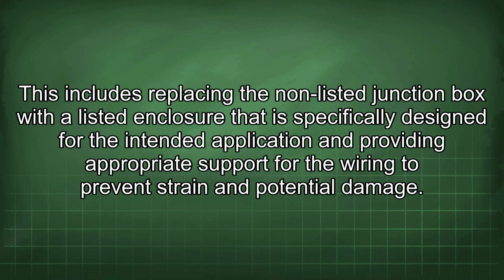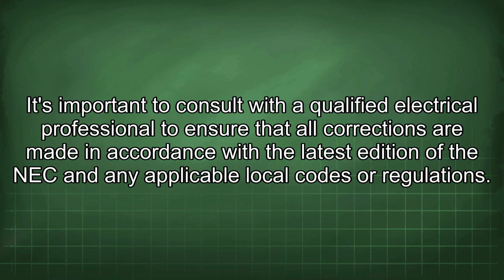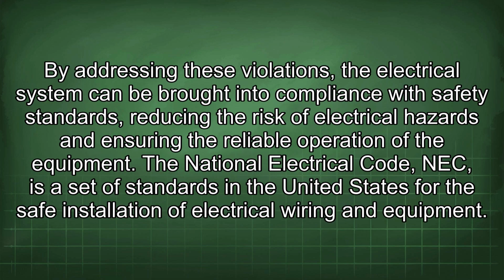This includes replacing the non-listed junction box with a listed enclosure that is specifically designed for the intended application and providing appropriate support for the wiring to prevent strain and potential damage. It's important to consult with a qualified electrical professional to ensure that all corrections are made in accordance with the latest edition of the NEC and any applicable local codes or regulations. By addressing these violations, the electrical system can be brought into compliance with safety standards, reducing the risk of electrical hazards and ensuring the reliable operation of the equipment.